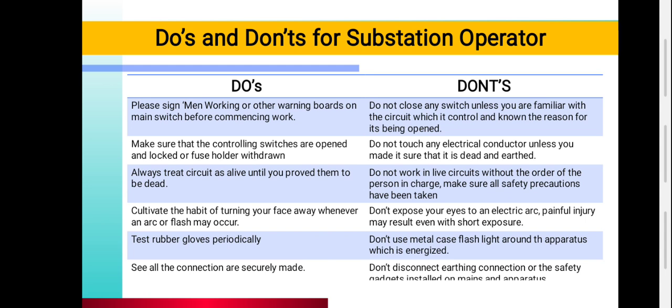Make sure that the controlling switch is open and locked, or the fuse holder is withdrawn. If you are touching any switch, make sure it is open — meaning there is no supply source — or that it is locked, or that the main supply fuse holder has been removed. Do not touch any electrical conductor unless you make sure it is dead or earthed.